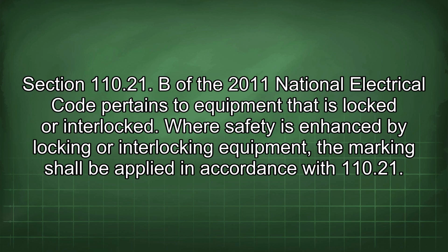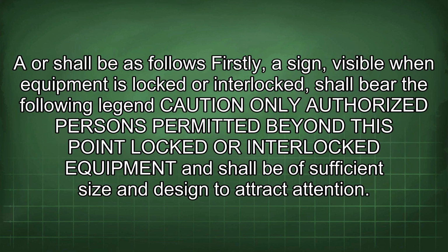Where safety is enhanced by locking or interlocking equipment, the marking shall be applied in accordance with 110.21(A) or (B) as follows. Firstly, a sign, visible when equipment is locked or interlocked, shall bear the following legend: "Caution, only authorized persons permitted beyond this point, locked or interlocked equipment," and shall be of sufficient size and designed to attract attention.